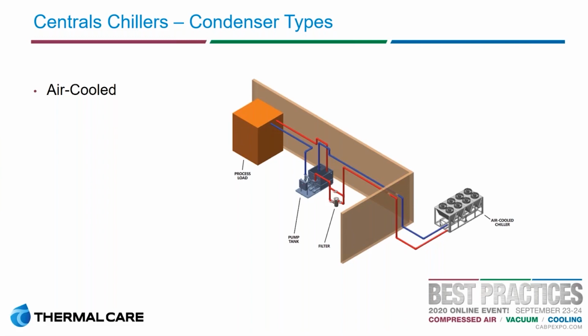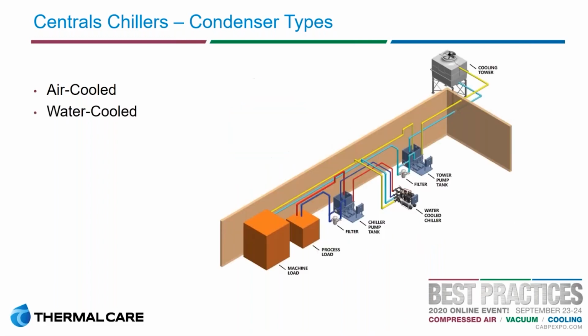So what's happening here is it's just the water that's going in and out. And so in an instance like this, because you have that chiller sitting outside, a lot of times you'll have to account for the ambient conditions that it would be exposed to. And so in this case, we could be operating at a temperature well above freezing as the set point of the chiller, but we'll still need to include a glycol solution within that water to protect it from the ambient condition it could be exposed to. So that's one of the things you must consider here.